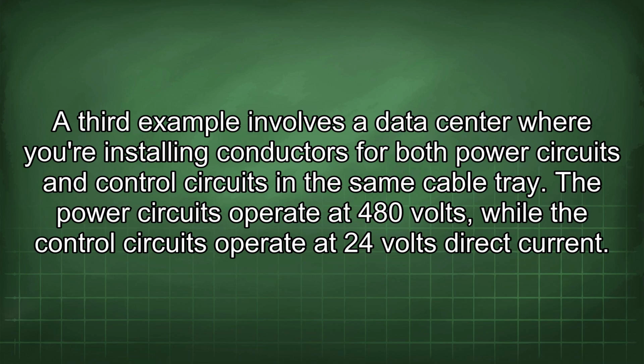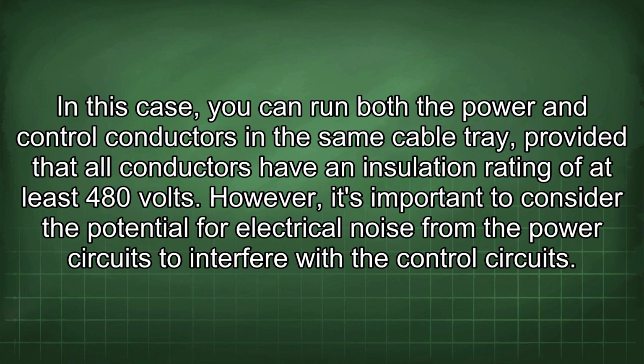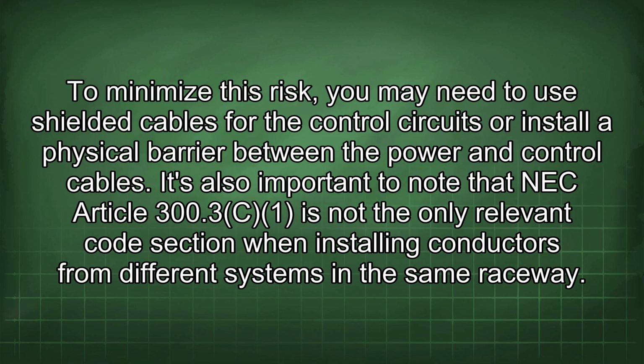A third example involves a data center where you're installing conductors for both power circuits and control circuits in the same cable tray. The power circuits operate at 480 volts, while the control circuits operate at 24 volts direct current. In this case, you can run both the power and control conductors in the same cable tray, provided that all conductors have an insulation rating of at least 480 volts. However, it's important to consider the potential for electrical noise from the power circuits to interfere with the control circuits. To minimize this risk, you may need to use shielded cables for the control circuits or install a physical barrier between the power and control cables.